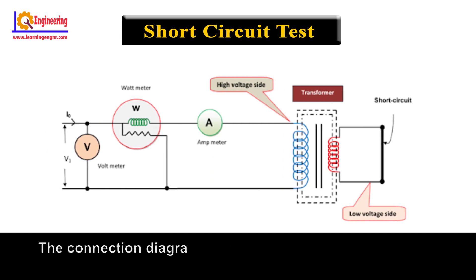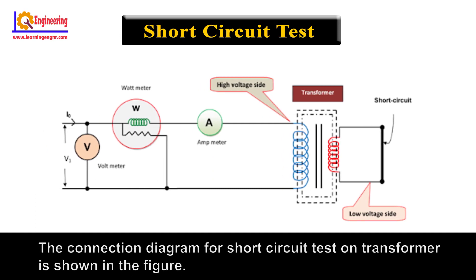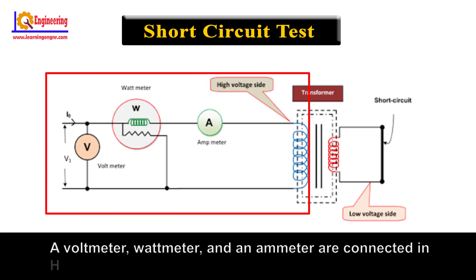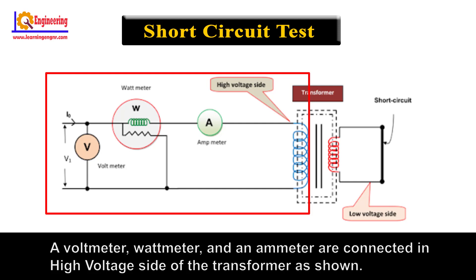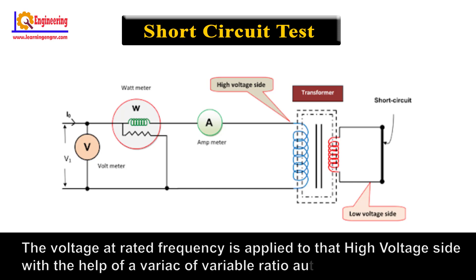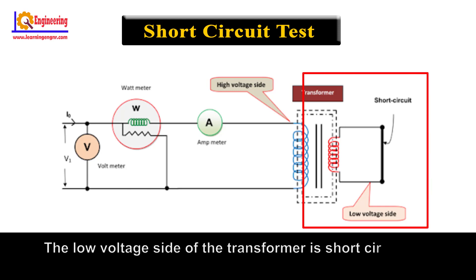The connection diagram for short circuit test on transformer is shown in the figure. A voltmeter, wattmeter, and an ammeter are connected in the high voltage side of the transformer as shown. The voltage at rated frequency is applied to that high voltage side with the help of a variac, or variable ratio auto transformer. The low voltage side of the transformer is short circuited.